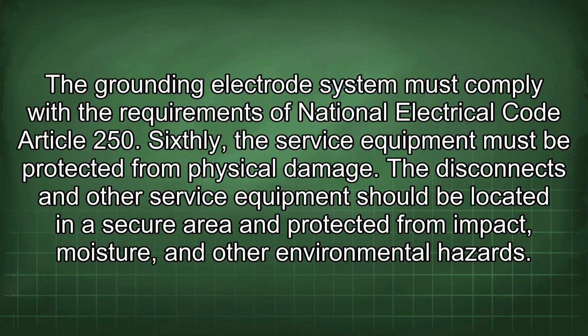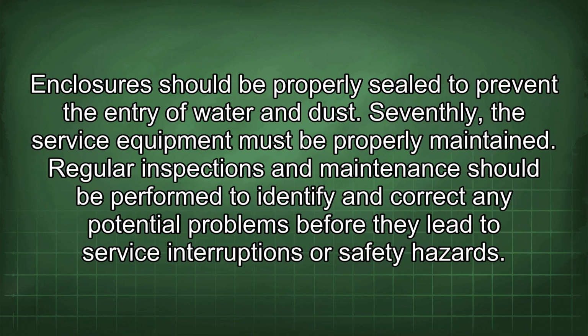Sixthly, the service equipment must be protected from physical damage. The disconnects and other service equipment should be located in a secure area and protected from impact, moisture, and other environmental hazards. Enclosures should be properly sealed to prevent the entry of water and dust.